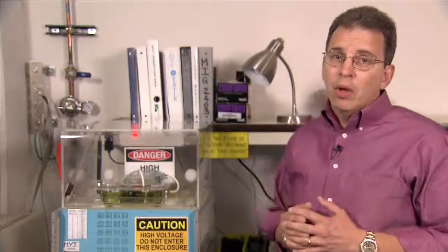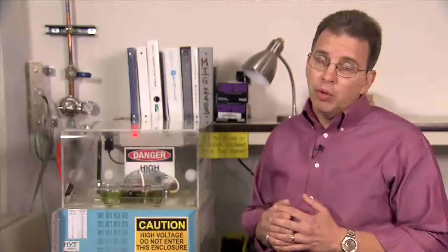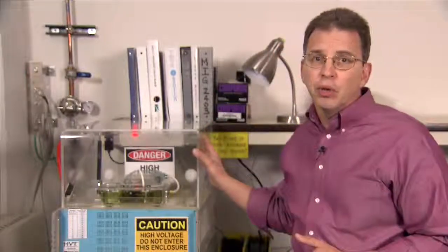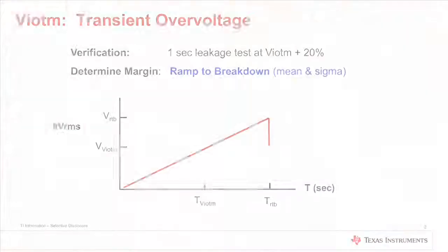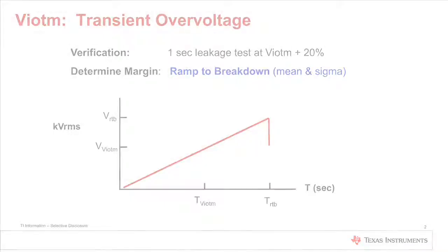In our lab, we also want to stress the isolators to determine margin to Viotm by testing to the actual failure point with a ramp to breakdown test. Now, due to the high voltages required and package creepage and clearance limitations, this testing is performed in a dielectric oil to ensure the breakdown occurs through the isolation barrier during the test, rather than through the air or across the package. And we compare the ramp to breakdown voltage distribution, mean and width, to the transient overvoltage specification in order to determine our margin to Viotm.